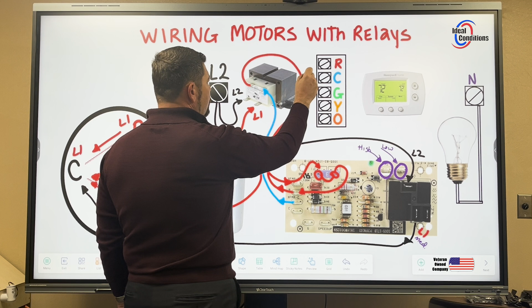I'm going to go ahead and erase these lines here so we don't confuse anybody. Just rewind that if you need to. Now we're going to take 24 volts out of our terminal block and run it into our thermostat, and then we're going to take common. Instead of going back to the transformer, we can just take common back to here or here. It does not matter. I'm going to take it back to the board. But first, I've got to make it to the air handler through my low voltage wire. Then I can come down here, and as you can see, I'm drawing an arrow as an input because my path literally is from here back to here. So everything on the left-hand side of the board is done.